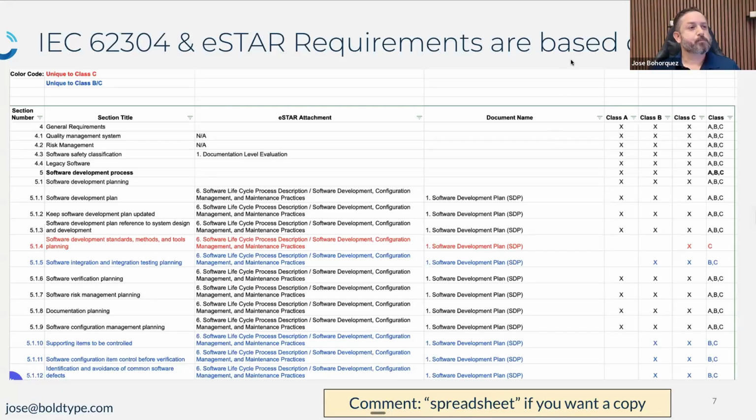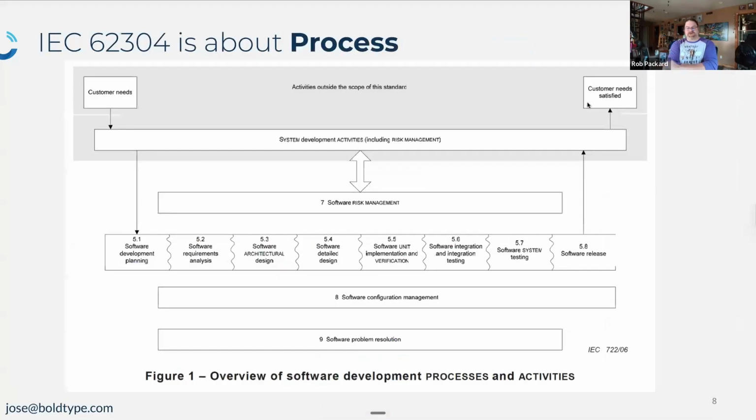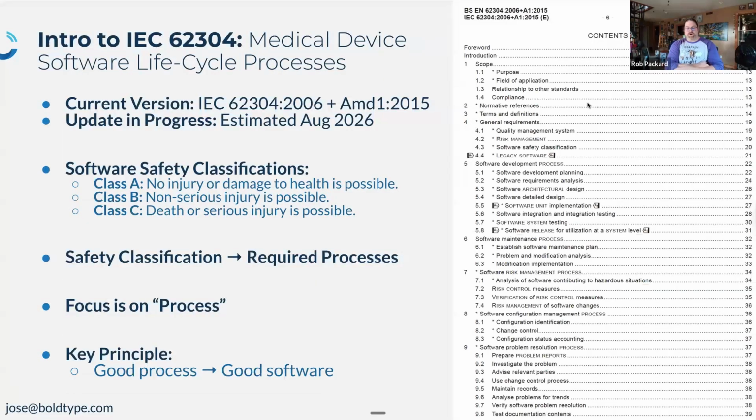Okay, cool. There was a really good one in there about the new version of 62304. I know you personally are very up to date on that. I made the comment, they were asking if the eSTAR and the process are likely to change with the new standard. And I would say absolutely yes. But at the same time, I'd also absolutely say that it's not going to happen in 26 because the FDA takes 6 to 12 months to recognize the standard to start with, and we don't know how it will impact it yet.